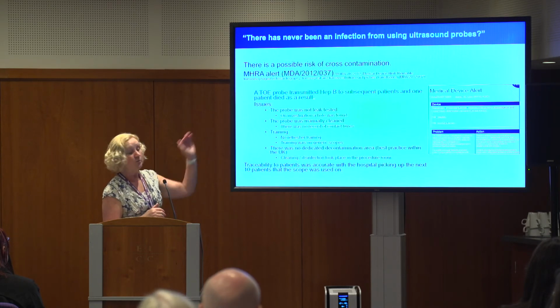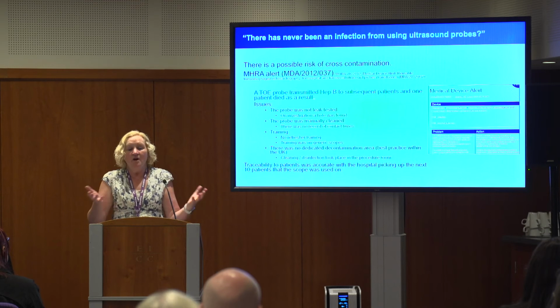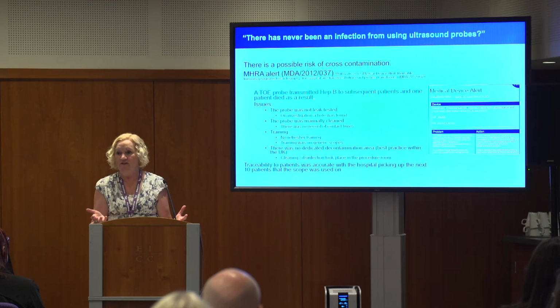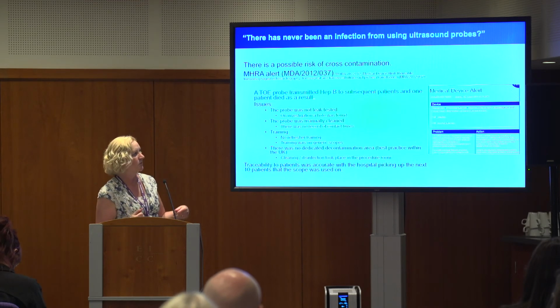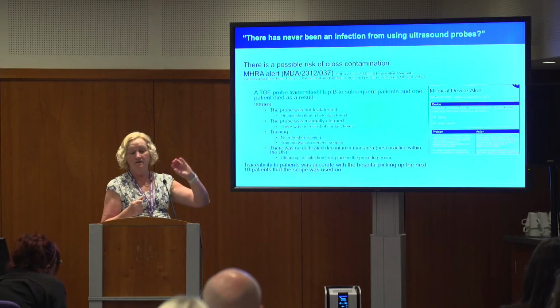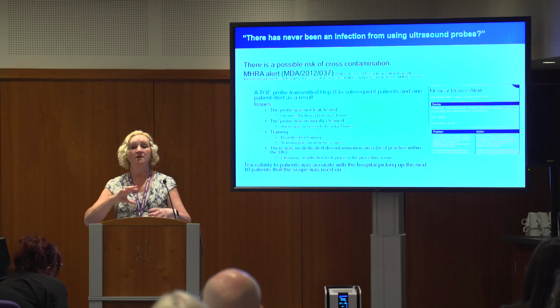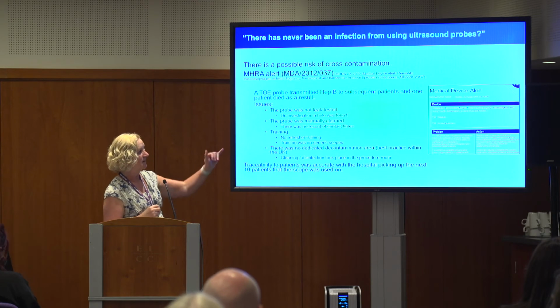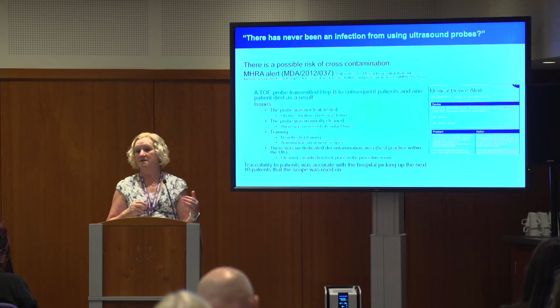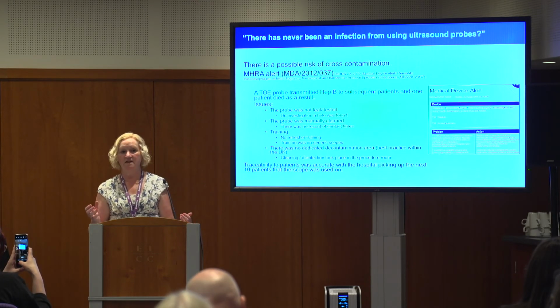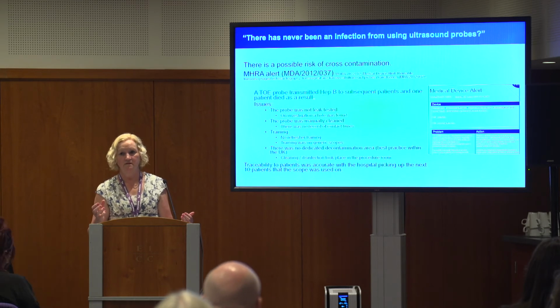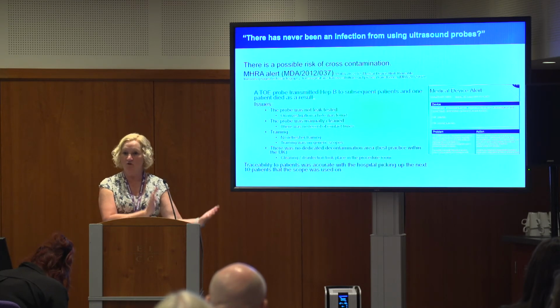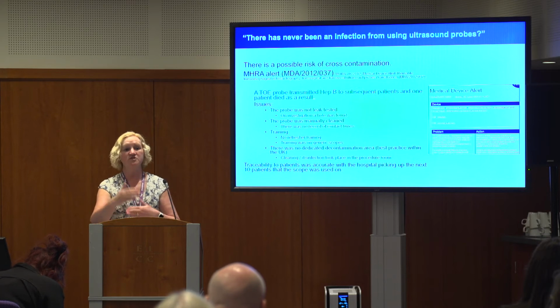So it wasn't leak rate tested. You can't test most probes for leak rate. You don't know whether they've got a hole in them. This one, you could use a scope vault, which would pressurise it. The probe was manually cleaned. There was no record of contact times. So no one knew, even though they'd got a system in place, there wasn't a record of how long it had been cleaned for.